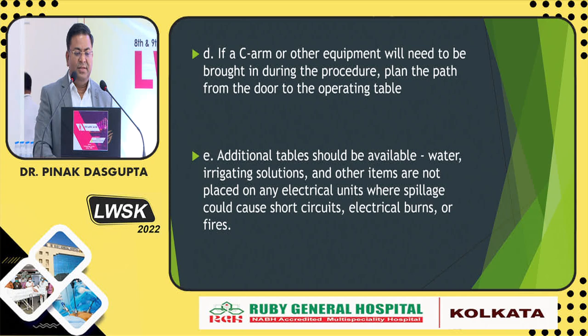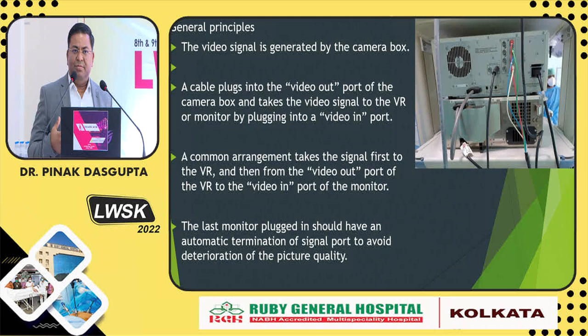One should be aware of all the plugs. It's a little cumbersome, but once you get used to it, it's simple. The camera processing unit will have an output from which the video signals are sent out, going either to the recording system or to the monitor. In the monitor it will be video in. So from the camera processing unit, video out goes to the monitor's video in, so that whatever processed image comes out from the processing unit is reflected on the monitor.